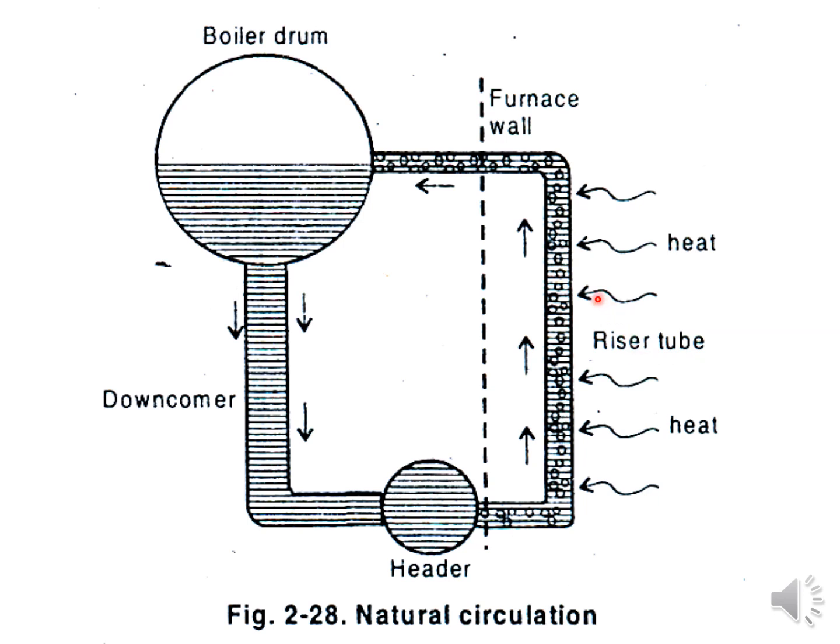See, whenever we heat the water, what happens to the water? Water is going to lose its density and it is going to rise up. So this raised water is coming back to the boiler drum, and whatever water is purely in liquid form or cold water is going to come back here. So this is naturally going to circulate. There is no pump or anything we are going to use in this system.